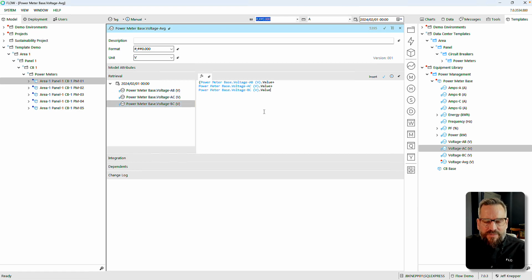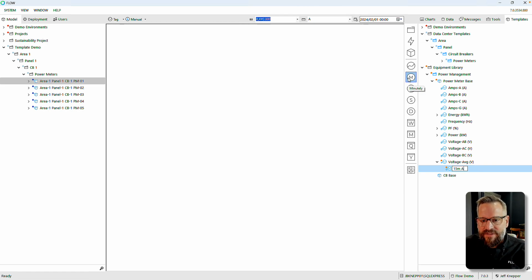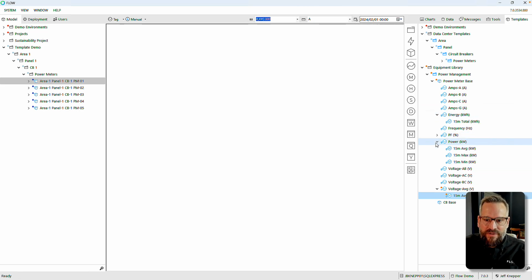As you've heard me talk about before, we're not storing the raw data inside of Flow. That raw data is still sitting in the historian. I've now created a memory tag that will function like it was raw data whenever it's called. And we're going to call it every 15 minutes and ask it to output an average of the raw data for the last 15 minutes. And then we will average that into a 15-minute measure that we then store.